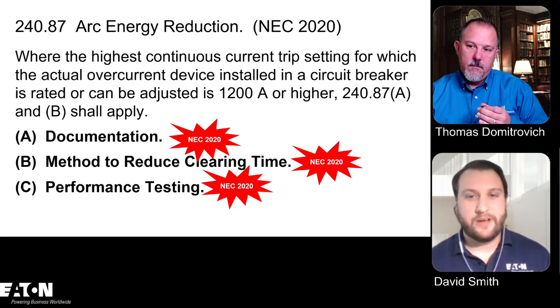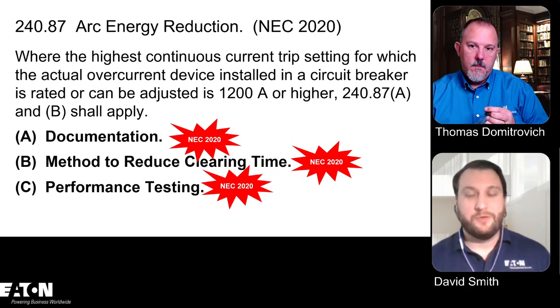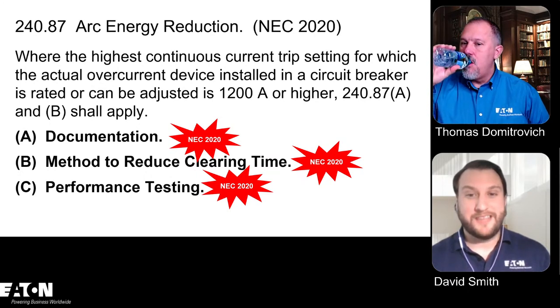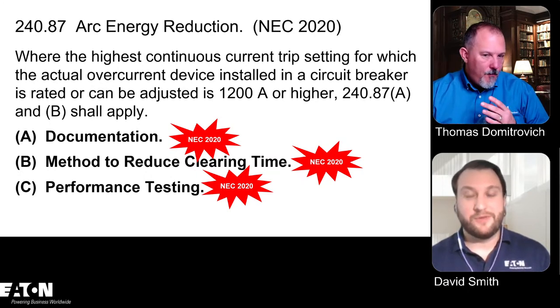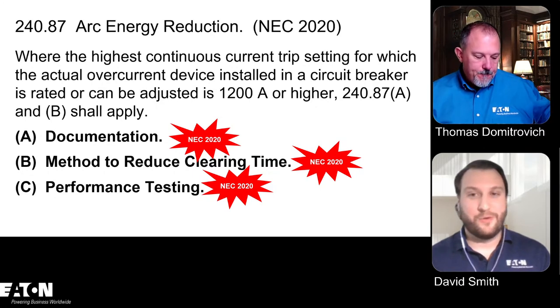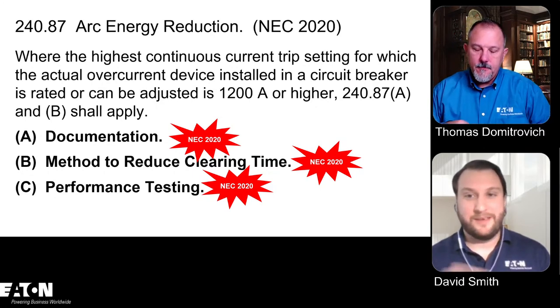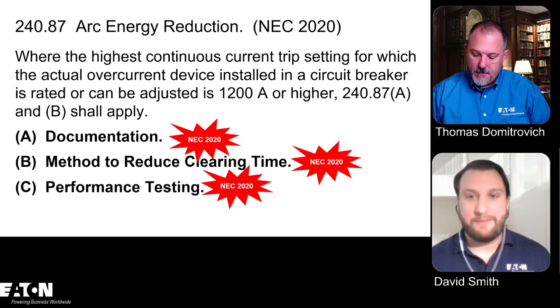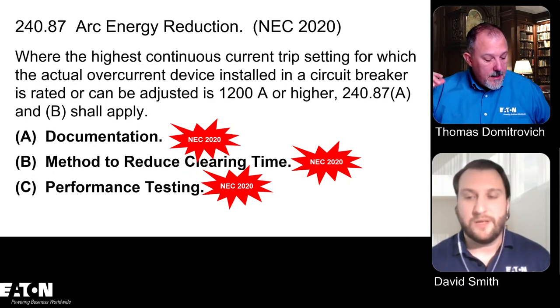I would imagine the documentation goes into, you would need performance testing documented. And so therefore, in order to get A to be compliant, you would need to have performance testing, which would go on the documentation itself. And so you're picking up C, even though it's not listed in that parent section, I guess, of 240.87.